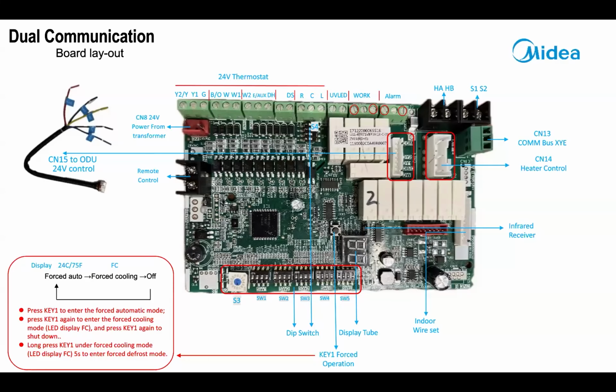All right, CN14, let's go around. Wire set. So this is indoor wire set. These two connectors here are the interconnecting cables that go between the display board and the main board. CN14 is your heater control. That's where, if you're using an auxiliary heater, you're going to plug in your auxiliary heater. It actually doesn't look like this anymore. Now it's changed to a red 5-pin connector. That's for the three-stage heat.